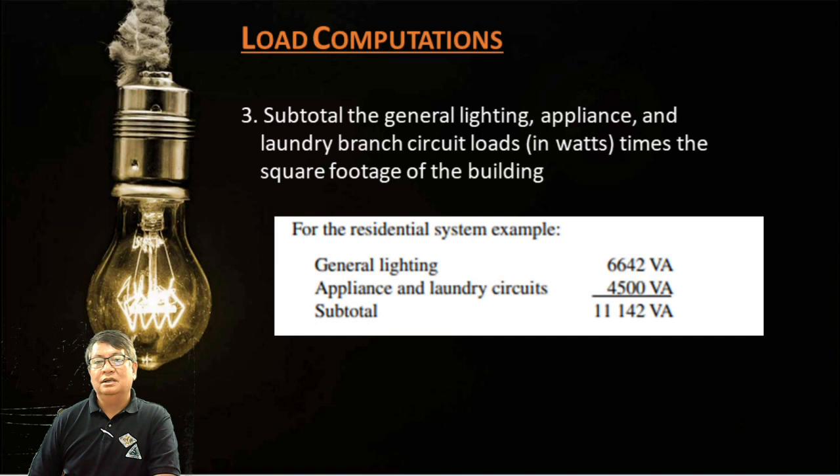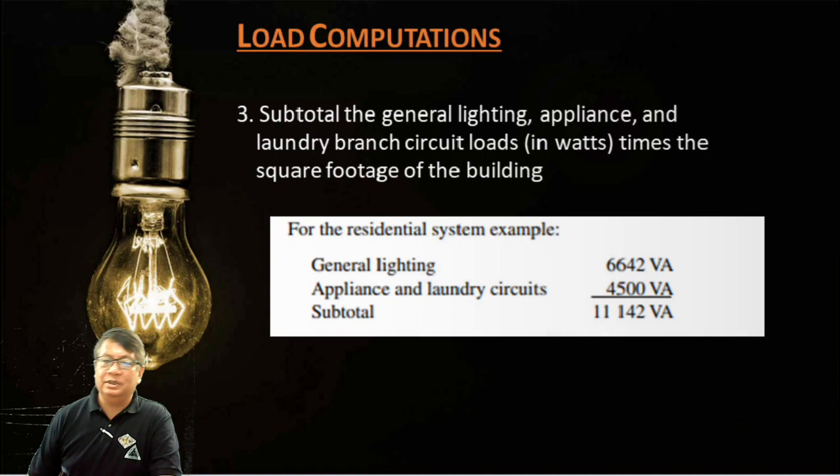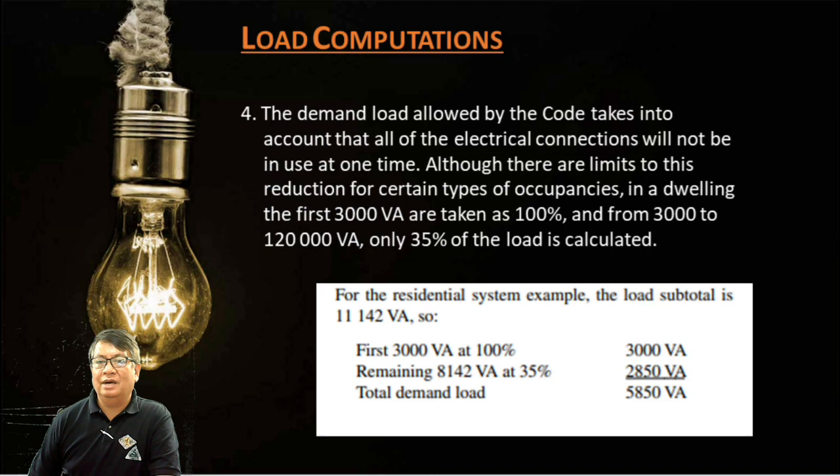Okay, so for the appliance, the similar thing here. Then we have the subtotal. To solve for the subtotal, we have more or less the subtotal power requirement of 11,142. Apply tayo ng demand factor. Sa Philippine Electrical Code, marami tayong mga demand factor doon. Example lang po ito. For 3,000 volt-amperes, we have 100%. The remaining is 35%. Example lang po ito.